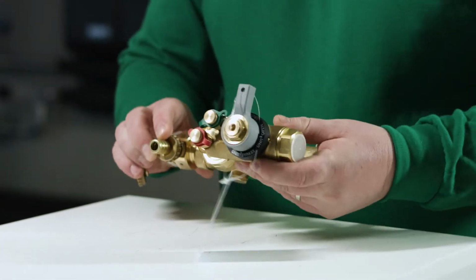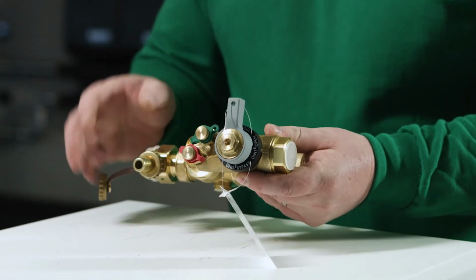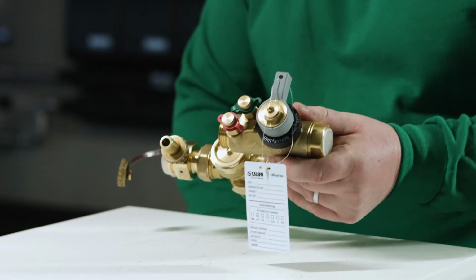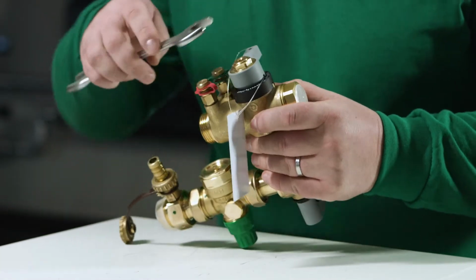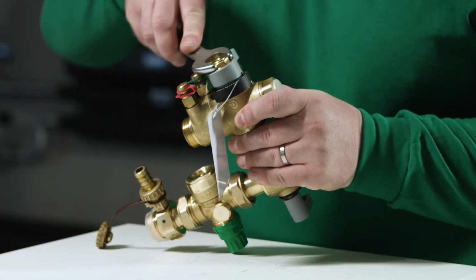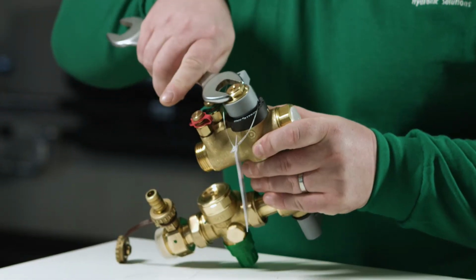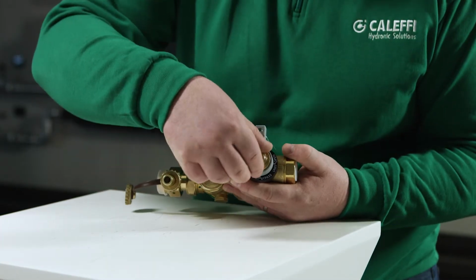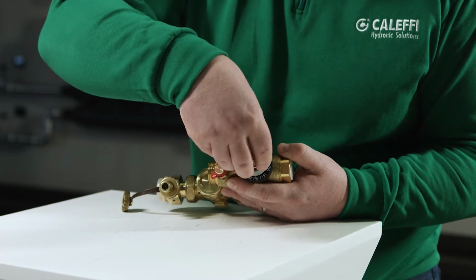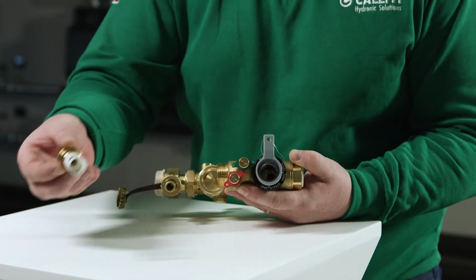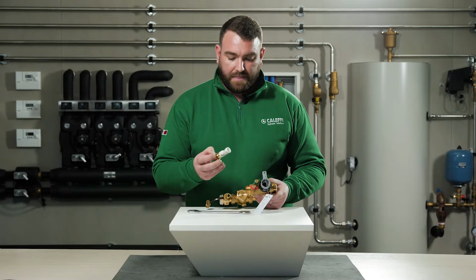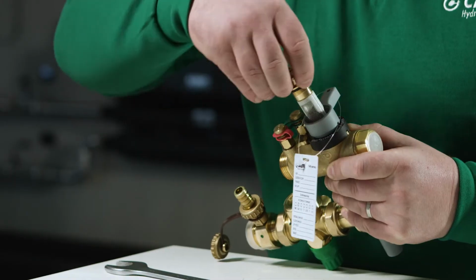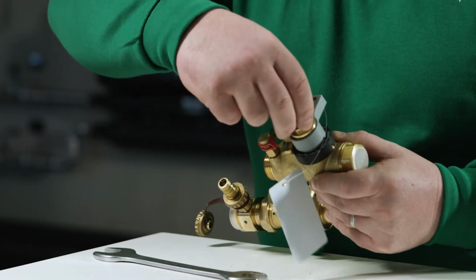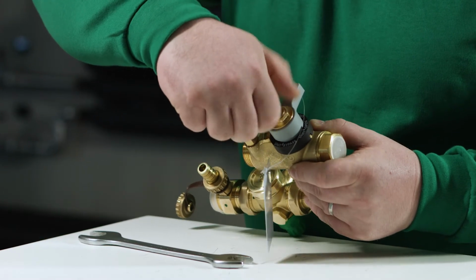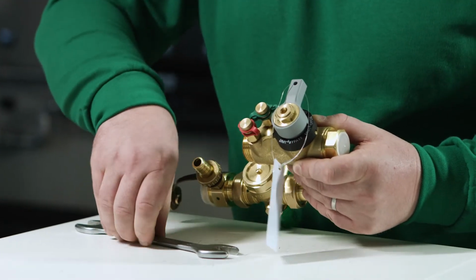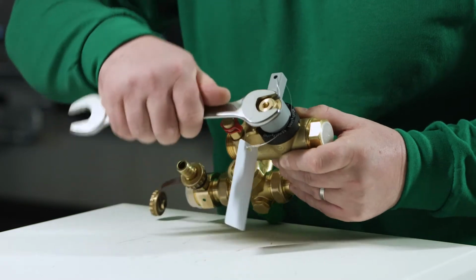To remove the strainer, we need to ensure that both of the isolation valves are in the closed position. We take our spanner, where we loosen the hexagonal nut. The strainer can then be easily removed and taken away to drain or taken away to clean. To reinstall the strainer, ensure that the slots line up within the body, reinsert and tighten the unit, ensuring that the unit is tight to prevent any leakages.